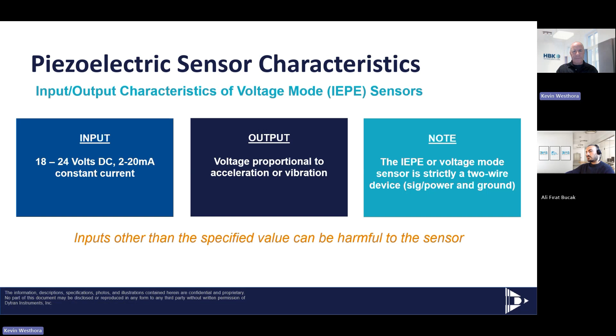And this is a very, very unique system. It's a 2-wire system, so you have signal on one wire and then power and ground on the same other wire. So for a single axis accelerometer, it's a coaxial cable, and for a triax, it's a 4-wire cable. For DC MEMS accelerometers, that's not the case. On a DC MEMS accelerometer, you would need 4 wires for a single axis, plus minus in, plus minus out, and you would need 12 wires for a triax. So the cable is much easier to deal with on an IEPE accelerometer versus a DC MEMS accelerometer. And then this last part here is related to this 18 to 24 volts. Do not use any benchtop DC power to power up an IEPE sensor because you will destroy the accelerometer.